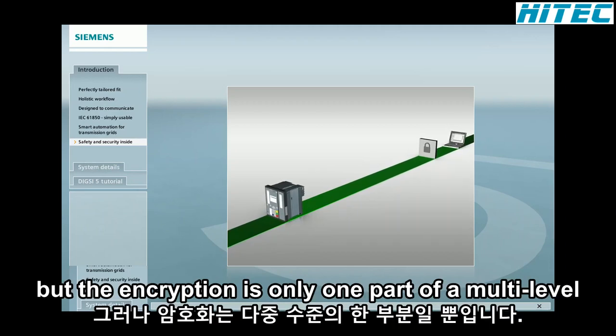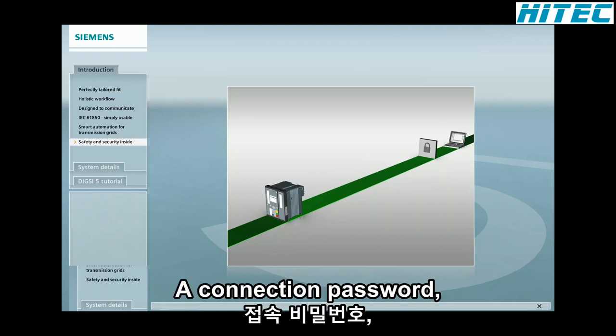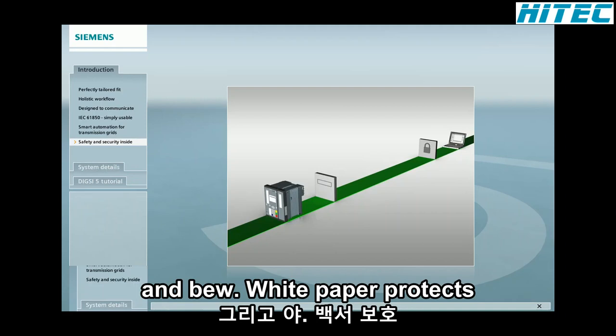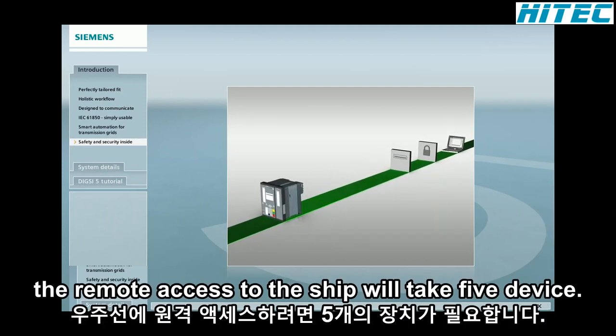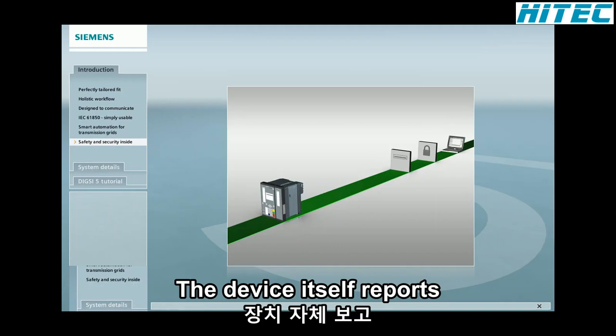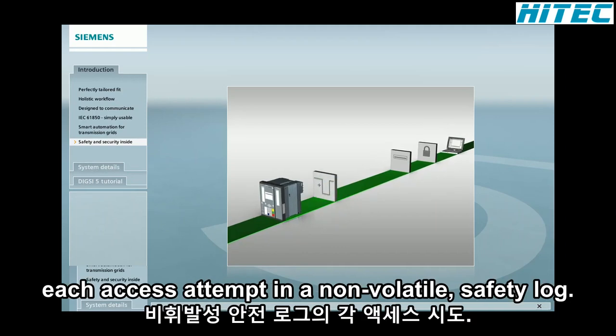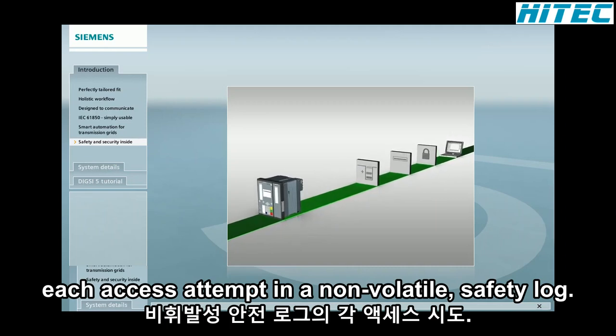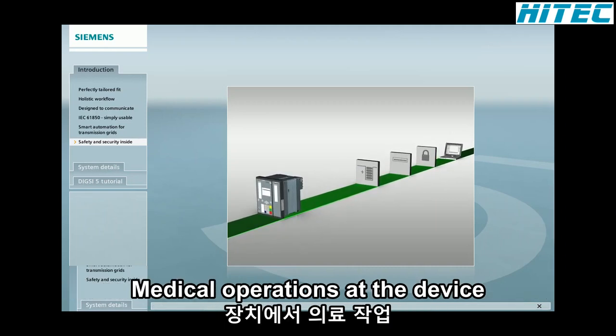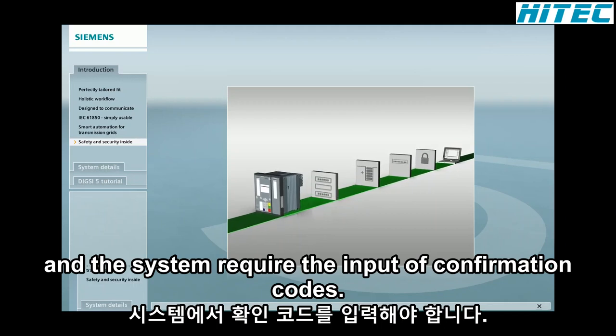But the encryption is only one part of a multi-level safety chain. A connection password, according to NERC CIP and BDEW white paper, protects the remote access to the SIPROTEC 5 device. The device itself records each access attempt in a non-volatile safety log. And safety-critical operations at the device and the system require the input of confirmation codes.